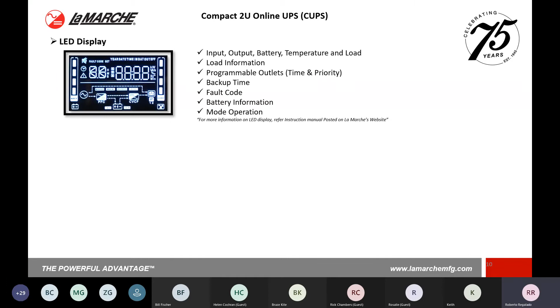You can designate or see your backup time, which you have to manually input. For example, backup time is calculated based on the internal battery pack of the module, but if you apply additional external battery packs, you'd have to manually update the amp hour rating so it calculates correctly. Fault codes and battery information are also shown on the display, and you can change the mode of operation as far as priorities on the AC or DC side.